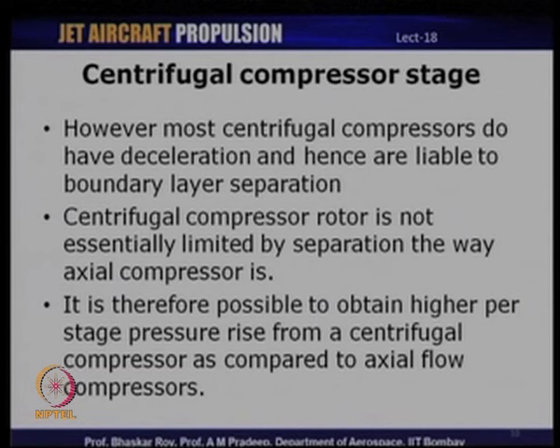Diffusion begins from the impeller outlet, continues in the vaneless space, and also in the diffuser vanes. In the diffuser, flow exiting the impeller gets decelerated with an associated pressure rise. The pressure rise mechanism in the diffuser is purely due to deceleration, unlike in the impeller where pressure rise has two components: one due to the centrifugal force field and one due to deceleration.